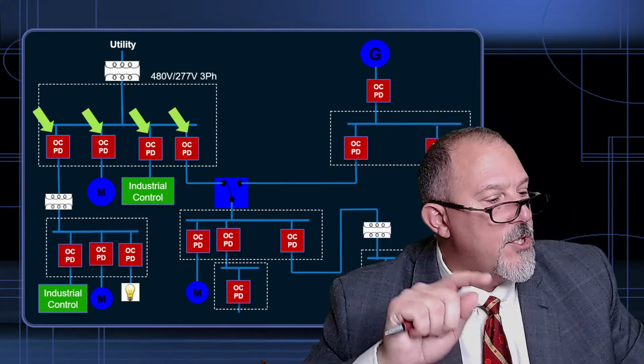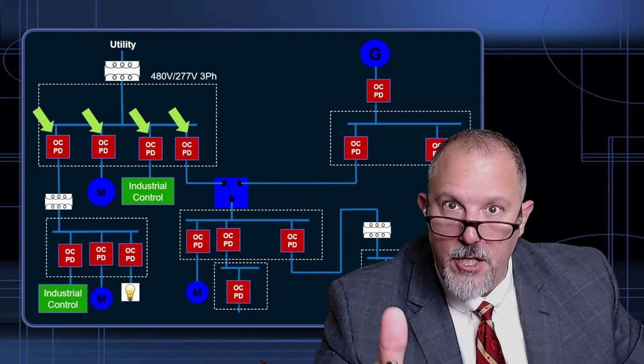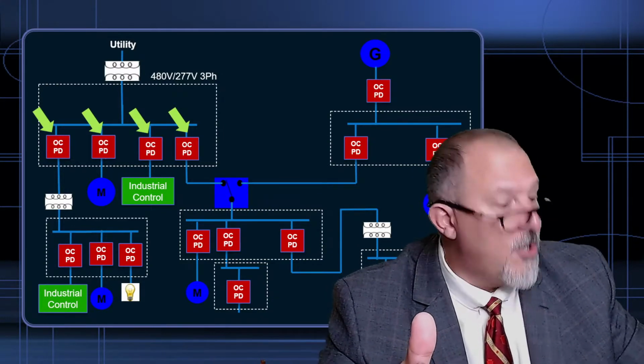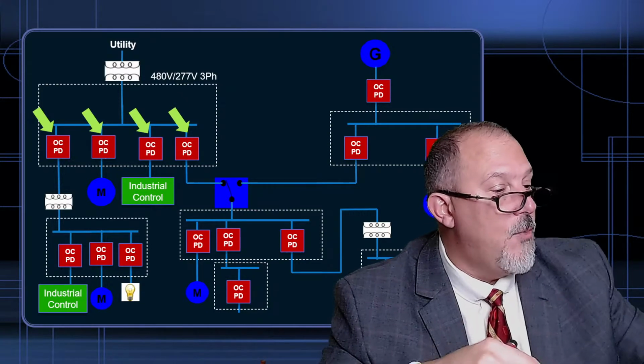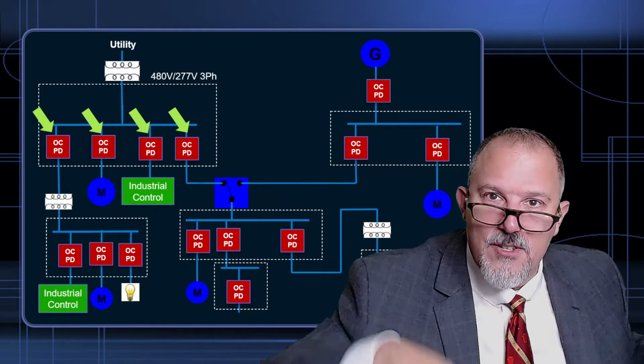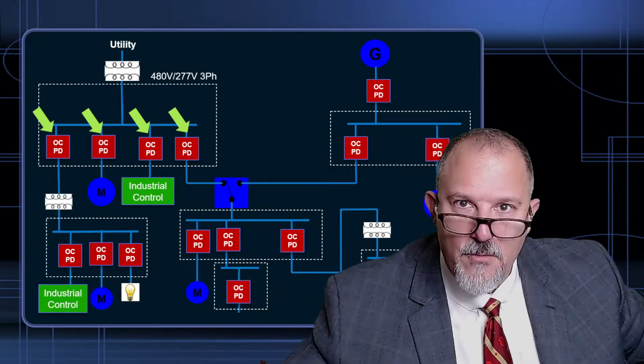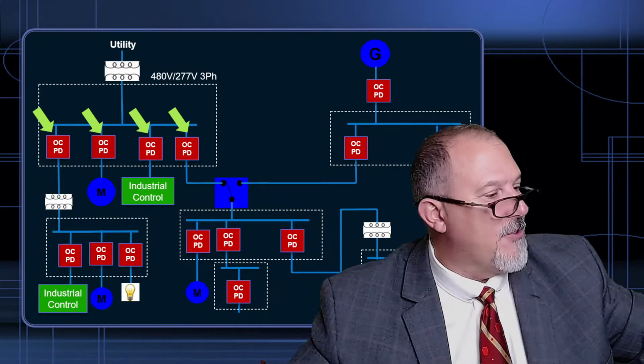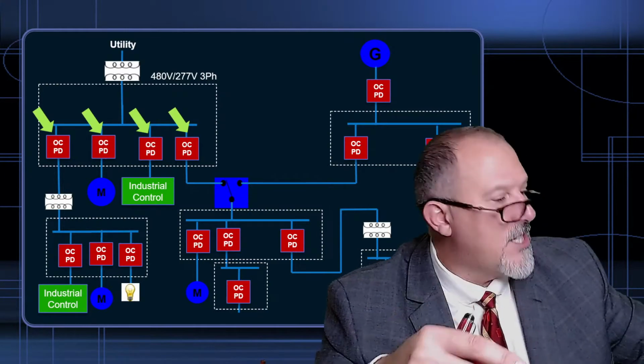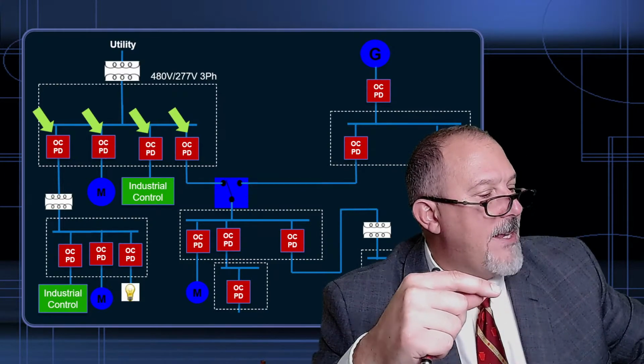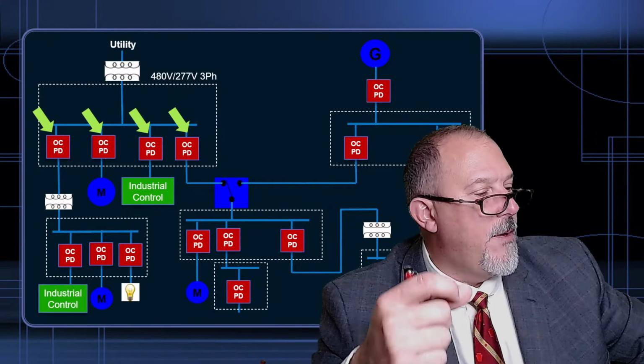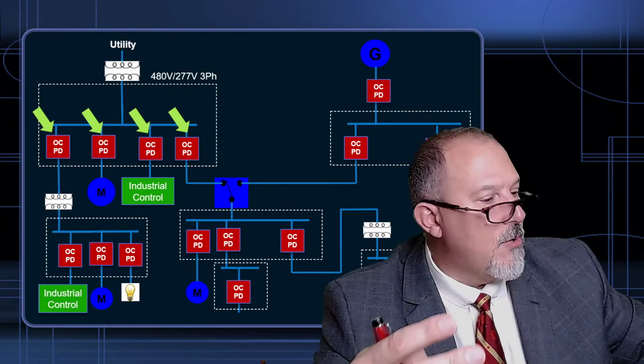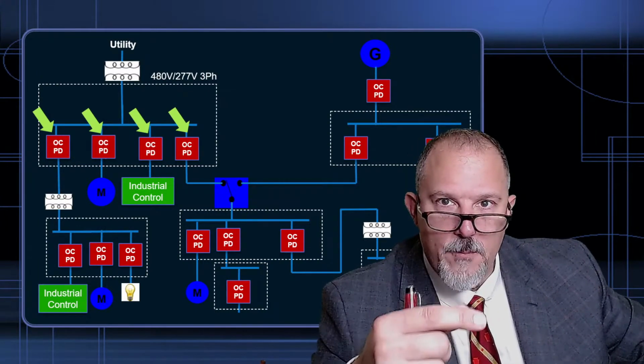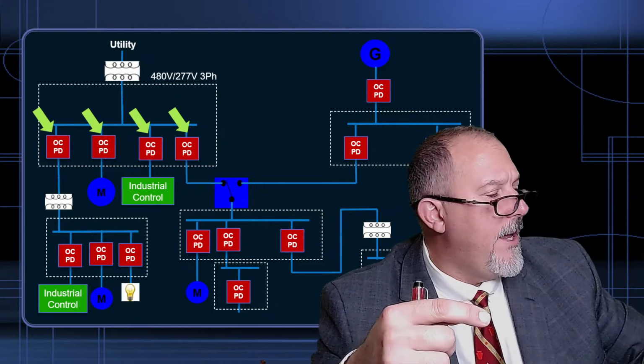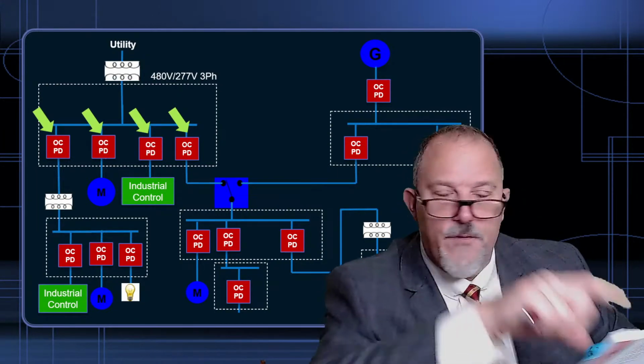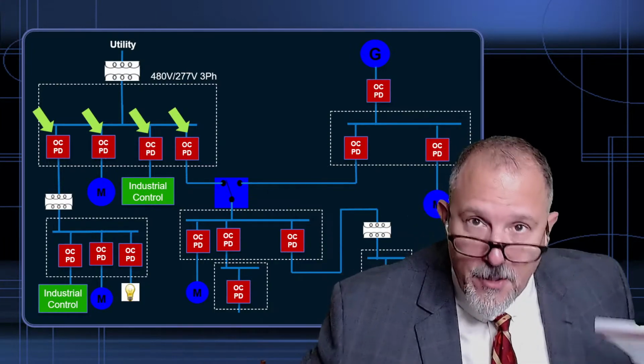And it says for panelboards from 240 to 600 volts, this is the information you need to know. You need to know the maximum available fault current, 25,000 amps. Well, that doesn't quite match up with this code. Remember, we weren't talking maximum, we were talking available fault current, not maximum available fault current. So this table requires a maximum available fault current. And then it has a clearing time, a maximum of 0.03 seconds, a 2-cycle clearing time for that overcurrent protective device, and then an 18-inch minimum working distance. And if you meet those parameters, you can determine how to dress.